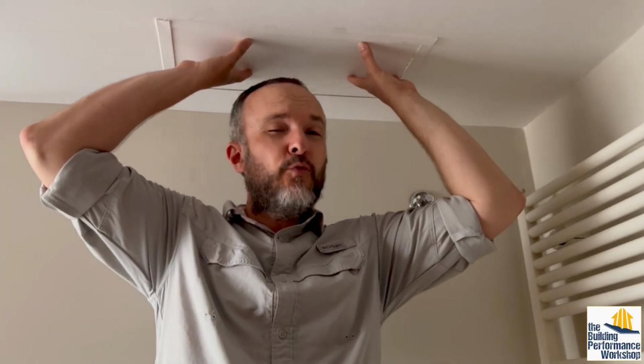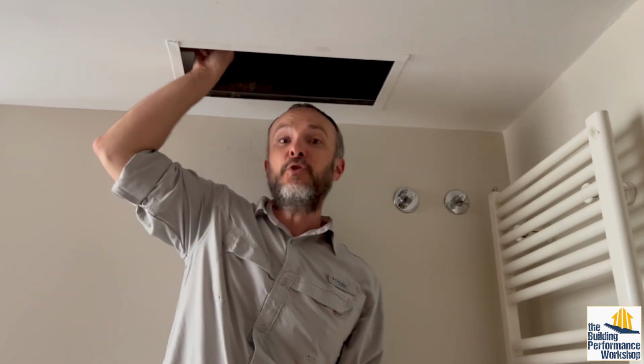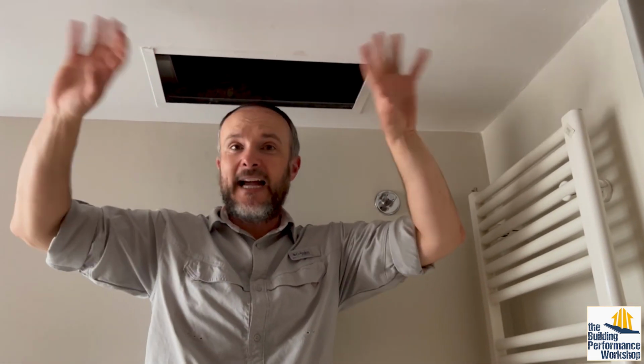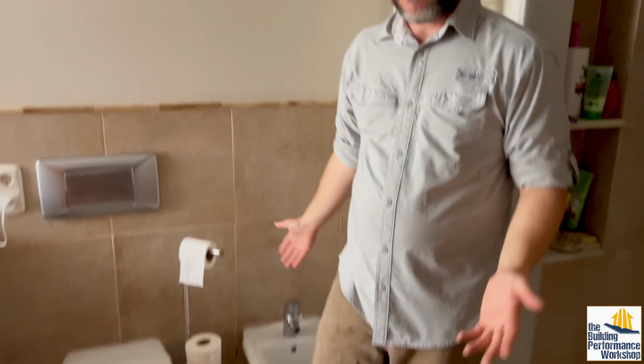The other thing that we could do is to just open up this access hatch, which would relieve a lot of the pressure of this unit, because the negative pressure is highest right next to the fans, which are right here. So if I take this off, now I've reduced the amount of depressurization in the entire ceiling plenum. That means partly that I'm not going to get any air pulled from the bedrooms at the far end here, or even from the living. Probably all the air is going to come right through this hole. But I'm standing in a bathroom. You do not want your return for your air conditioning coming from a bathroom for odor reasons or for humidity reasons.